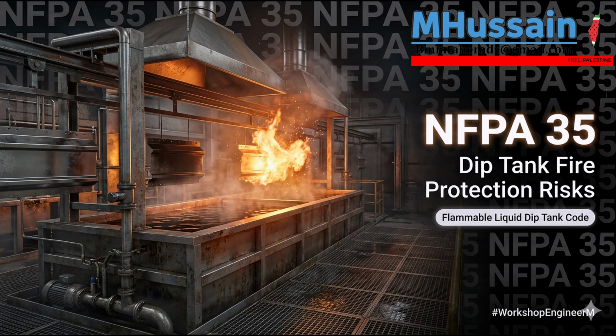But the code also extends a Class 1 Division 2 classification further out. Oh, it does. It generally extends from 5 feet out to 8 feet horizontally. And crucially, it covers the entire space up to 3 feet above the floor, extending out 25 feet horizontally. Because, as we established, the vapors sink. Exactly. The code anticipates that heavy vapor creeping across the floor. In a Division 2 area, explosive vapors aren't normally present, but they could be under abnormal conditions, like a leak.